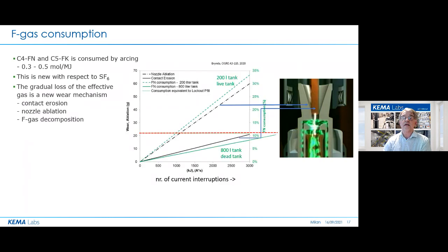Well, this is investigated, of course, and what you see here is a chart which shows the number of current interruptions. So this is showing the energy of the arc, and this is the wear during the life of a switching device. This line shows the ablation of the nozzle, which is reaching a limit at this point. The red line is the operation limit regarding the wear. Then we see the other one, the so-called arcing contact wear, which goes with this black line.